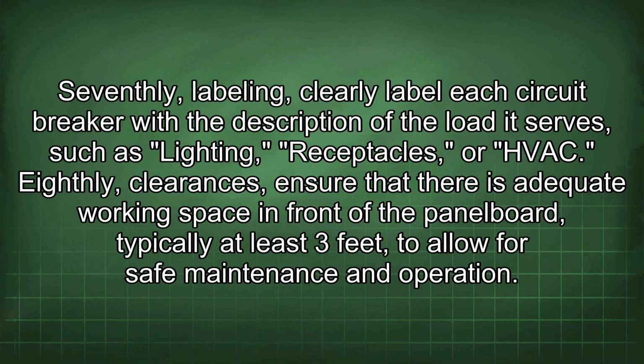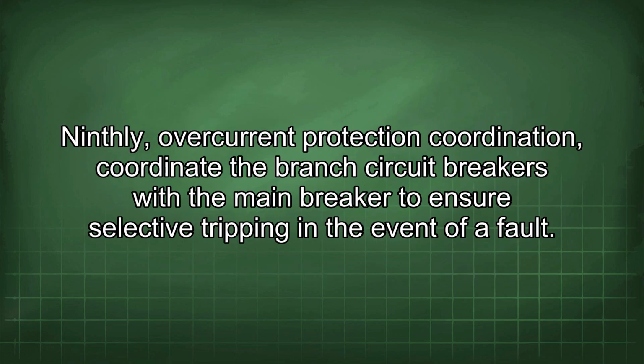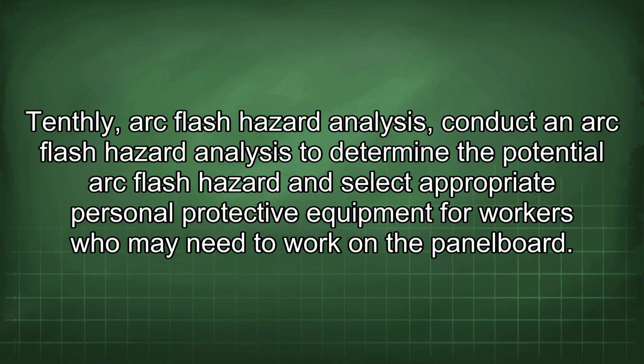Seventhly, labeling. Clearly label each circuit breaker with the description of the load it serves, such as lighting, receptacles, or HVAC. Eighthly, clearances. Ensure that there is adequate working space in front of the panelboard, typically at least 3 feet, to allow for safe maintenance and operation. Ninthly, overcurrent protection coordination. Coordinate the branch circuit breakers with the main breaker to ensure selective tripping in the event of a fault. Tenthly, arc flash hazard analysis.